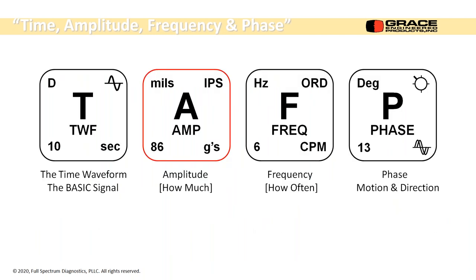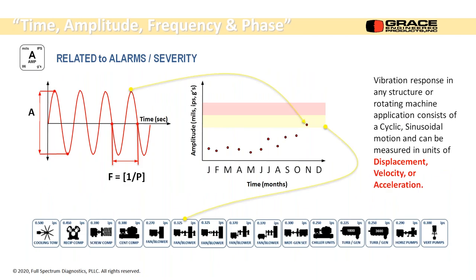Amplitude wise, how much? We talked briefly about this last Thursday. I'm logging the amplitude, and I've got one little reading here and I'm waiting for it to go into alarm. What is this alarm level? It's based on the machine. So I have a center hung direct coupled fan or blower system. My alarm level is going to be 0.325 inches per second.